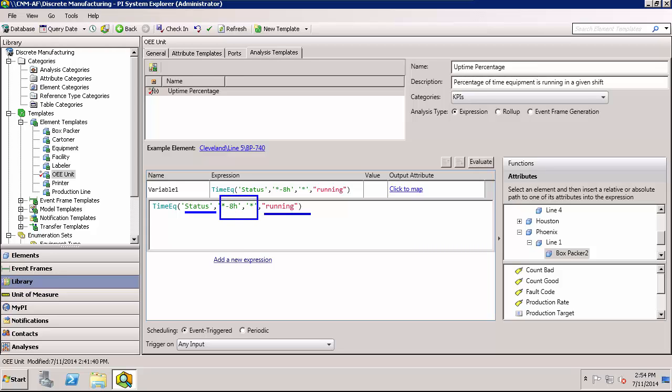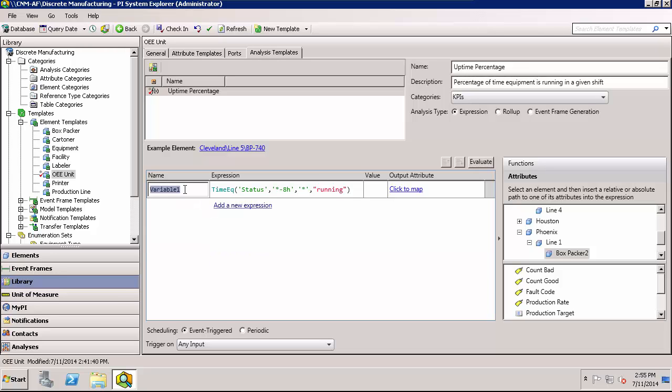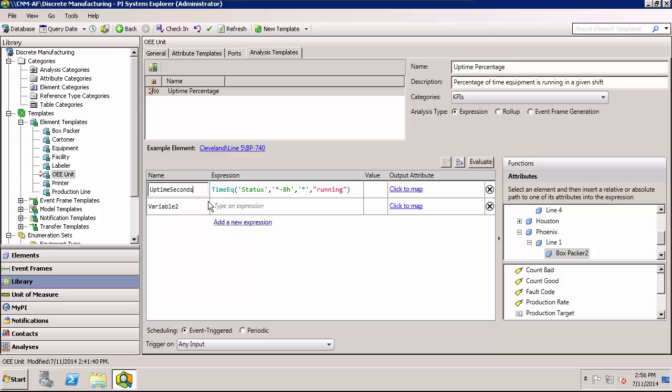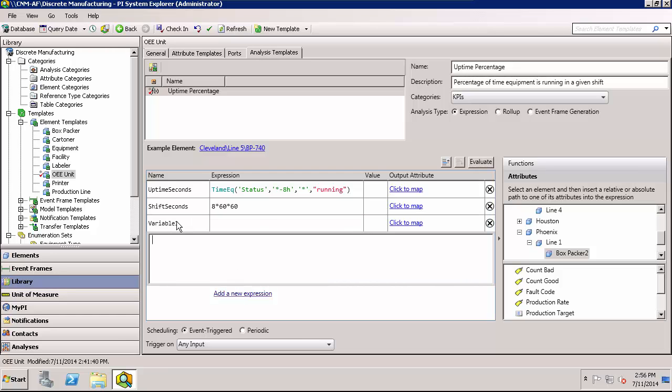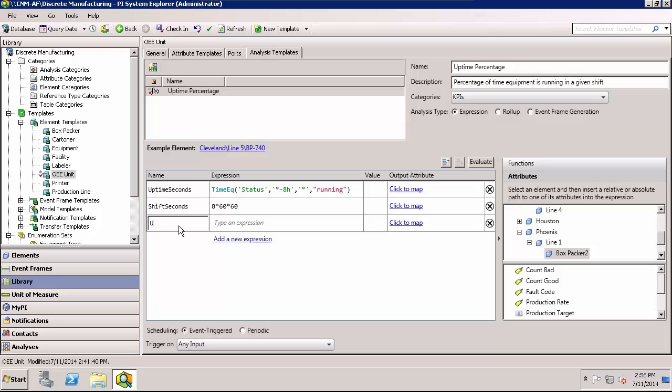But that's not actually my uptime percentage, which is what I really want. In order to get it into that format I would need to divide by the number of seconds in my shift, and then I would need to multiply that by 100%. I can keep typing and do that, but one of the really nice options is I have the ability to do multiple expressions to give them variable names and then they will be evaluated sequentially. So that's what I'm going to do in this case. And this just makes it easier to see how things were set up and for debugging purposes. I'll give this a name of uptime seconds. I'm not really able to put spaces in the name so I'll do it like that. And then my other expression, let's do the shift seconds or the number of seconds in a shift. And let's see, my shift is 8 hours long, and then there are 60 minutes in an hour and 60 seconds in a minute. And then I'll set up a final new expression for my uptime percent.